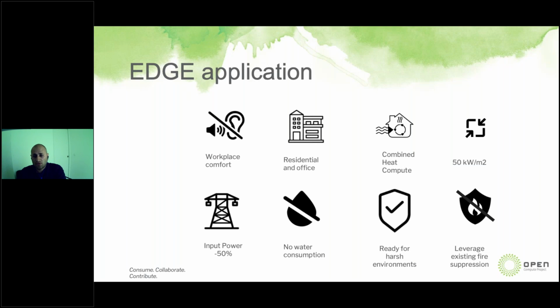Immersion solution excludes the noise of air ventilation. Silence in the data hall improves the comfort of the personnel. Server racks can be placed in office or residential areas. A modular immersed edge data center can be connected to the heating system in the building. Higher density reduces the surface demand. The power input is reduced 2 times.